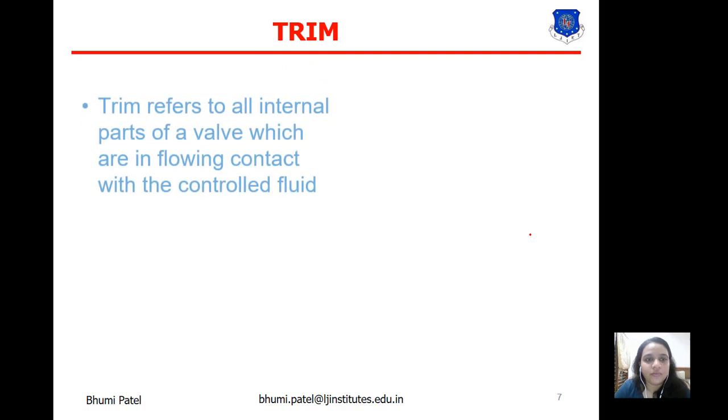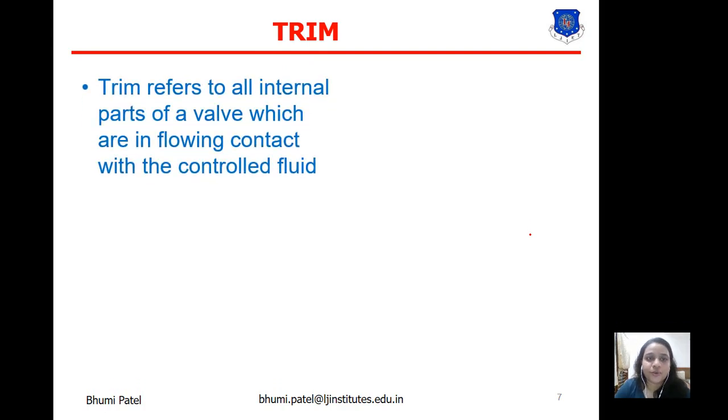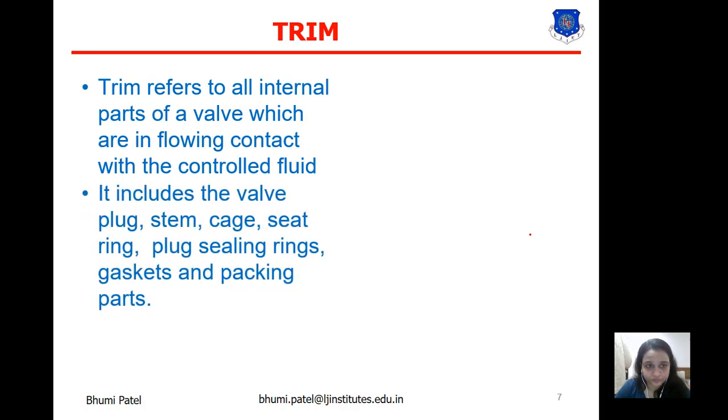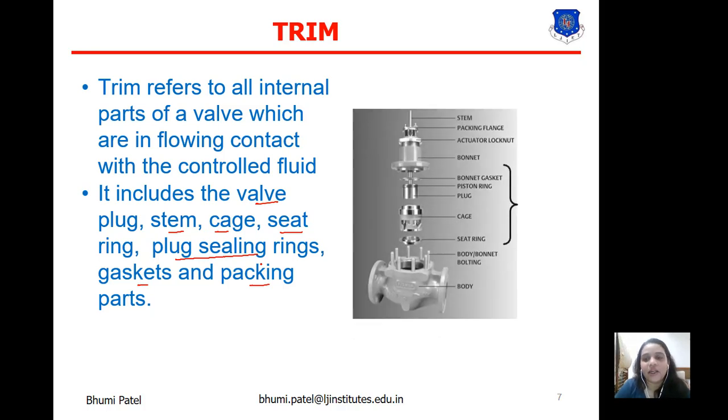What is trim? Trim refers to all internal parts of a valve which are in flowing contact with the control fluid. So trim includes the valve plug, stem, cage, seat ring, plug sealing ring, gasket and packing parts. So the major portion of the control valve is known as the trim.